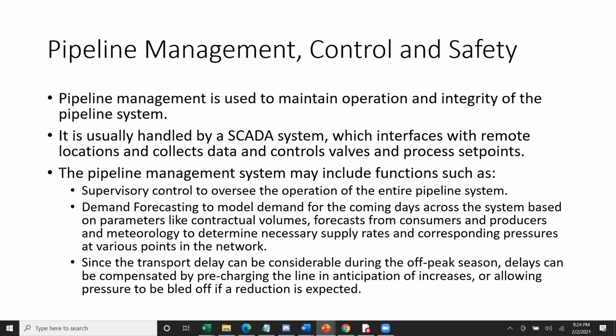The pipeline management system may include functions such as supervisory control to oversee the operation of the entire pipeline system, and demand forecasting to model demand of the coming days across the system based on parameters such as contractual volumes, forecasts from consumers and producers, and meteorology to determine the necessary supply rates and corresponding pressures at various points in the network. Since the transport delay can be considerable during the off-peak season, delays can be compensated by pre-charging the line in anticipation of increases or allowing the pressure to be bled off if a reduction is expected.